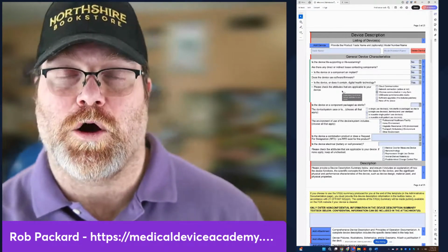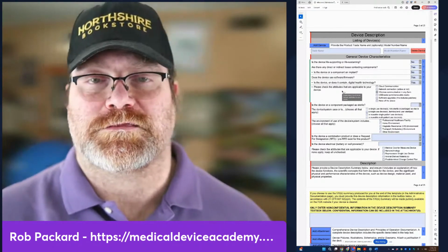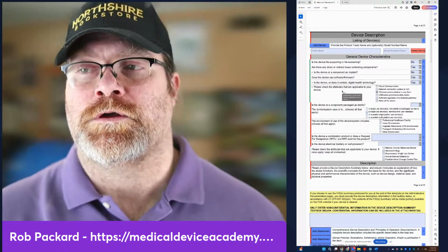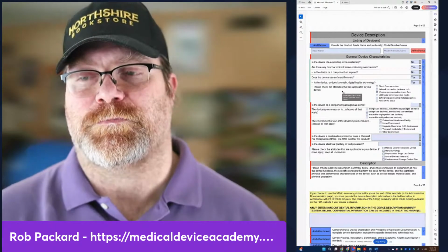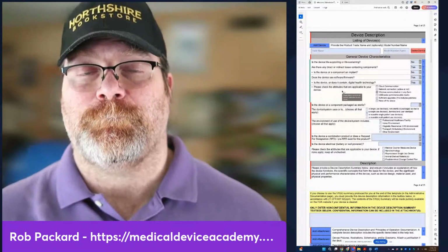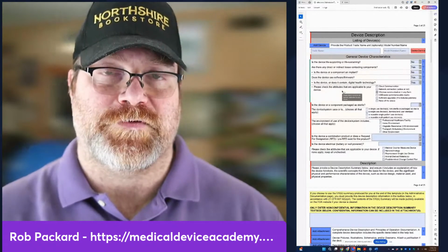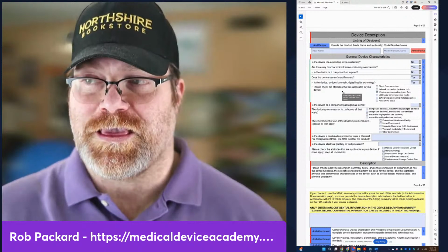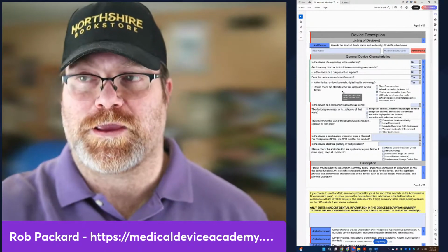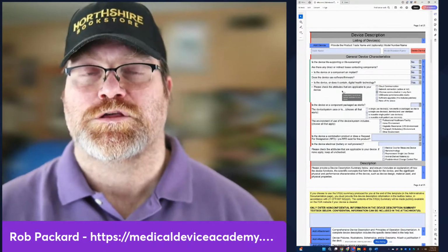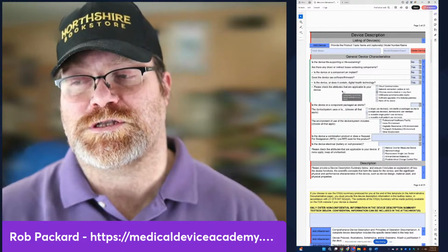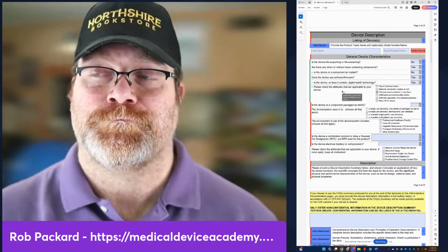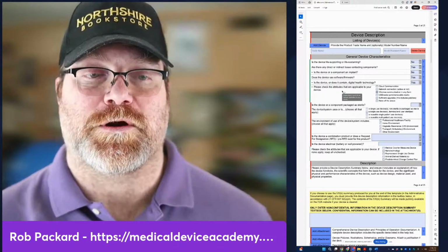Like we assumed it was sterile. You said it's non-sterile and they're going to autoclave it. Well, that would be an important detail to know. So that's why we ask you to provide some information that might be above and beyond what you would normally put in a device description, but it's important for your submissions. And the eSTAR has made some of those things where we can attach them in different places, so we can take them out of the device description template, but you still need the information in the submission somewhere. And the FDA makes it very clear where they want it.